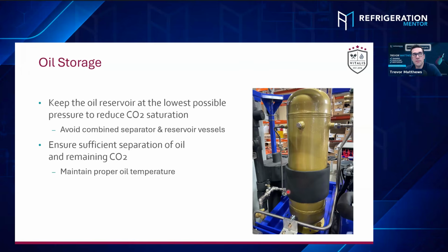One of the biggest things I've seen, especially over the last 5, 6 years doing all this CO₂ training, is that you used to think, okay, in the summertime they talk transcritical, it's super hot, that's when most of the issues happen. For me, having trained thousands of people, it's the wintertime where the biggest issues are, especially oil issues on these systems, where the reservoir fills up with CO₂ and you're sending direct CO₂ back to the compressor, or you lose pressure and you don't have enough pressure, because you've got to be above the suction pressure to move that oil.